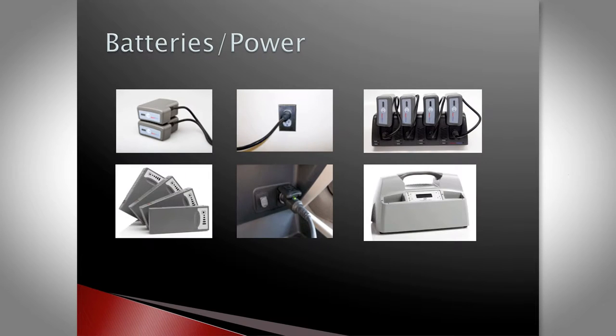All devices require batteries and must be attached to a battery source at all times or the device will not run. They must be attached to two batteries — it can run off one battery for only about 60 seconds. So patients will either be plugged into an external wall power source or have two batteries attached at all times.